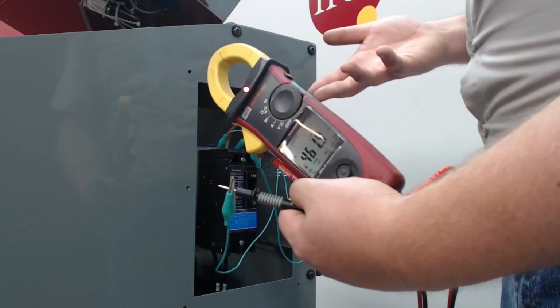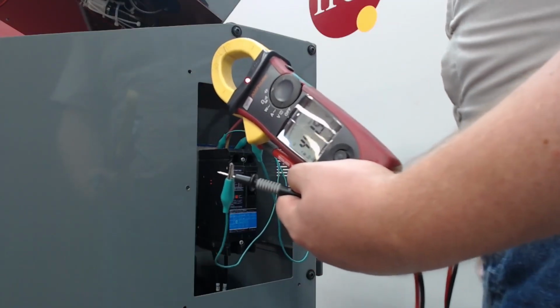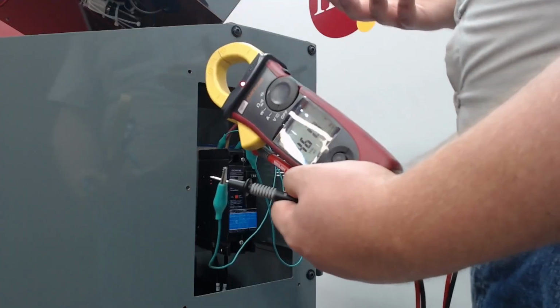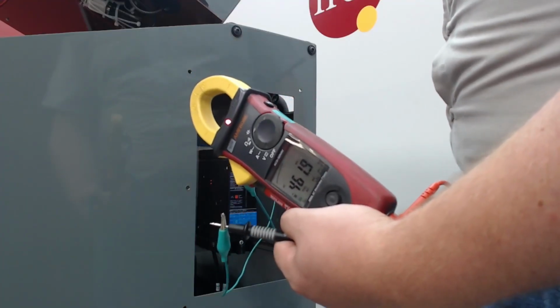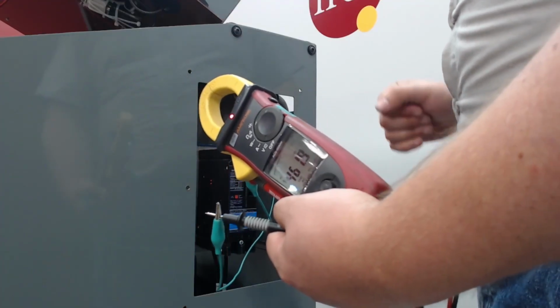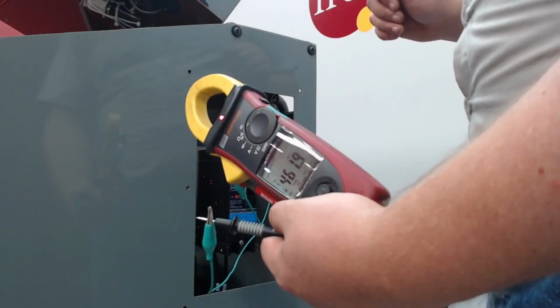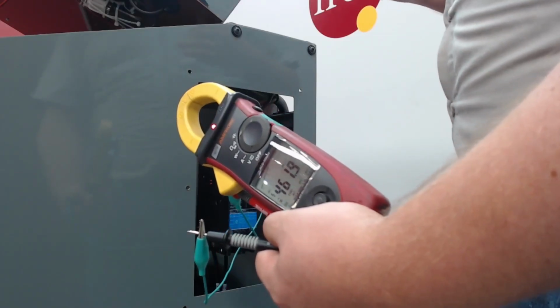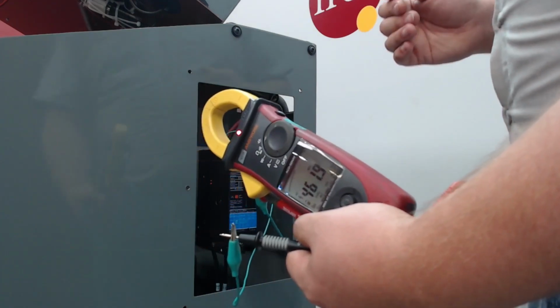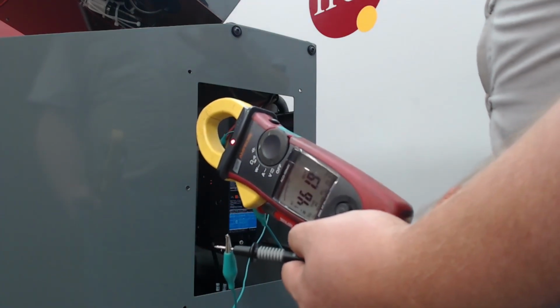You're going to be able to see that voltage drop to 420, 430. It shouldn't drop. It shouldn't drop at all. If you're seeing droppage, then your facility does not have enough power. You don't have a dedicated line. There really could be multiple reasons, but the problem is actually at your facility.